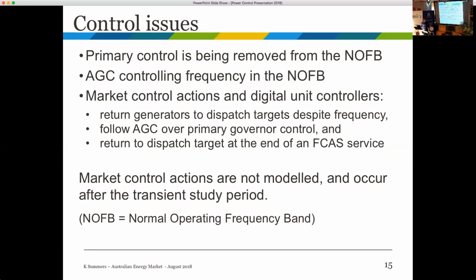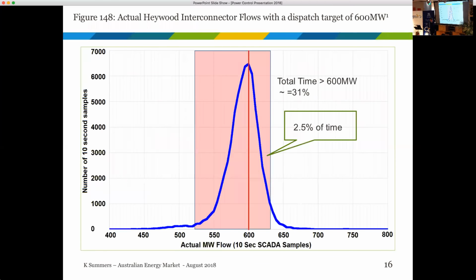Just to highlight what this looks like in terms of system security, this is a chart from the System Black report. I'll run through this quickly, and I'd recommend people read the paper referenced at the end. Here, the target for control was 600 megawatts on the Heywood Interconnector, and these are the actual megawatt flows. If you go over the red line, you're actually insecure, and if you stay down here, you're secure.